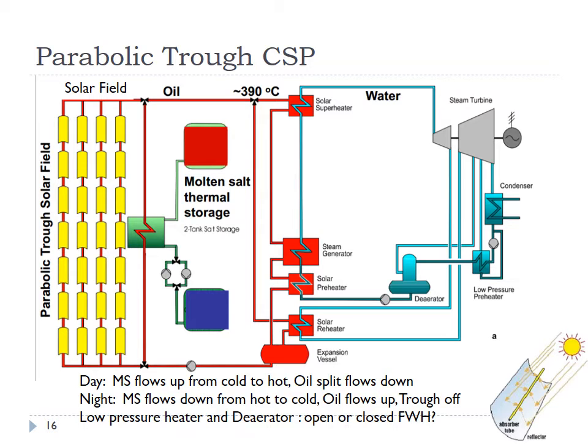After the second stage, we have some steam being sent to the closed feed water heater labeled here as the low pressure preheater. Finally, after the third stage of the LP turbine, that steam goes to a condenser, and then that liquid is combined with the liquid from the closed feed water heater, pumped up to the pressure of the deaerator, and then mixed with that liquid.